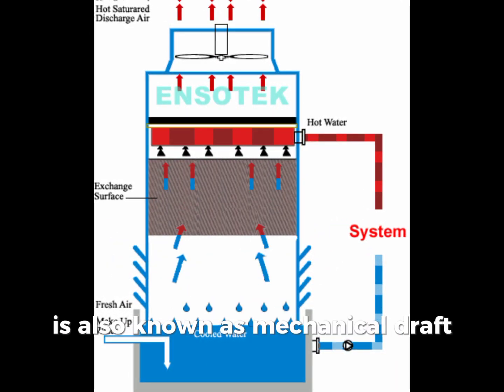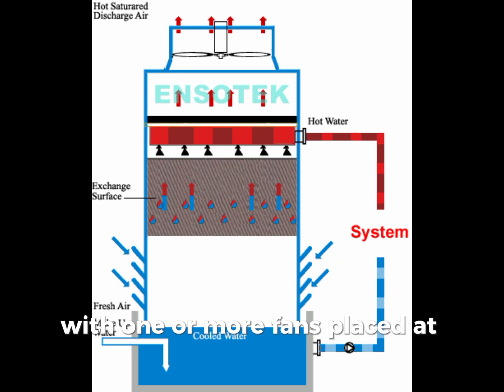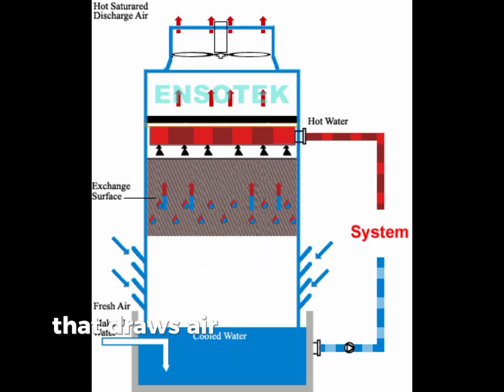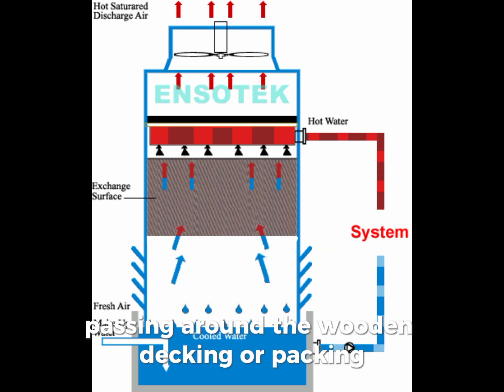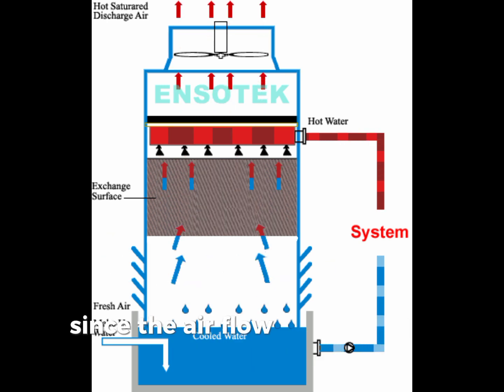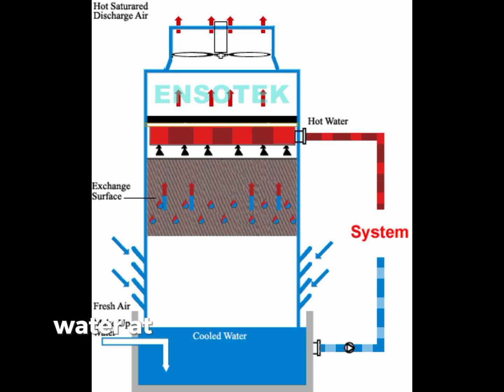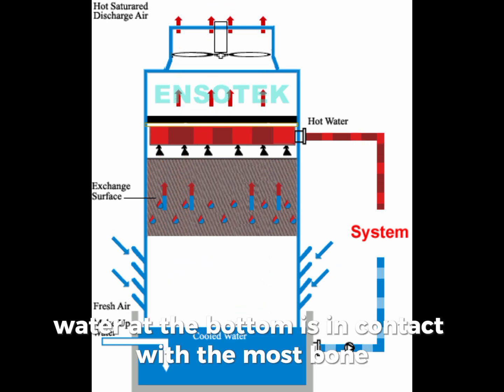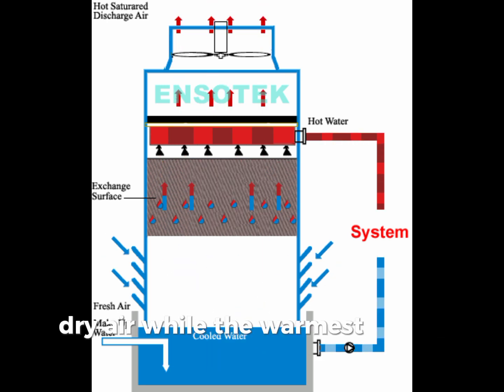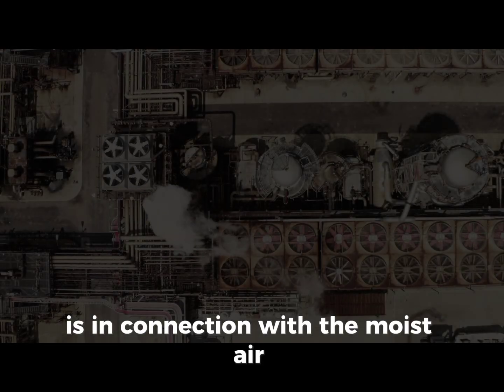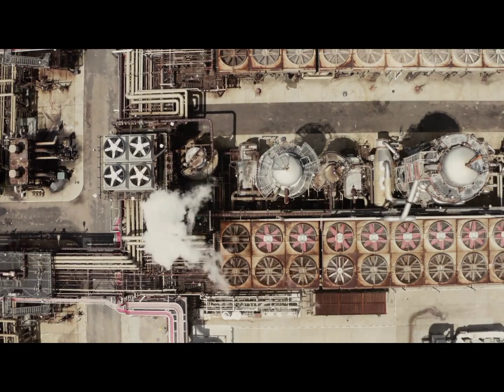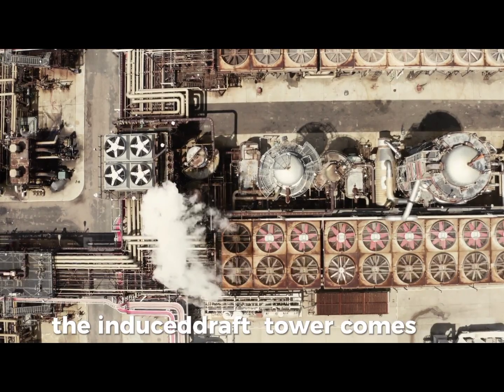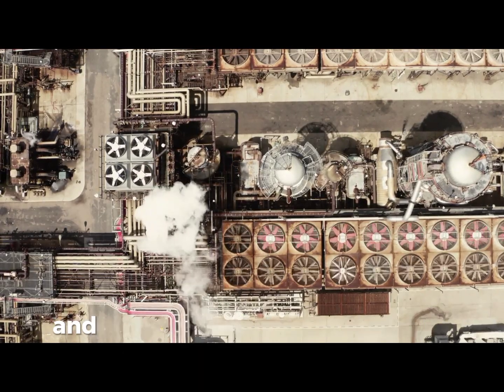An induced draft cooling tower is also known as a mechanical draft tower, with one or more fans placed at the top of the tower that draws air upwards, facing the downward flow of water passing around the wooden decking or packing. Since the airflow is counter to the water flow, the most chilled water at the bottom is in contact with the driest air, while the warmest water at the top is in contact with the most moisture, resulting in increased heat transfer efficiency.